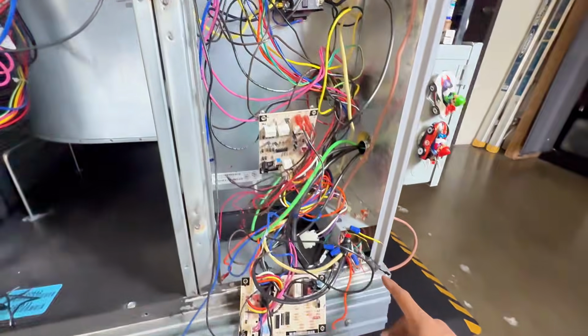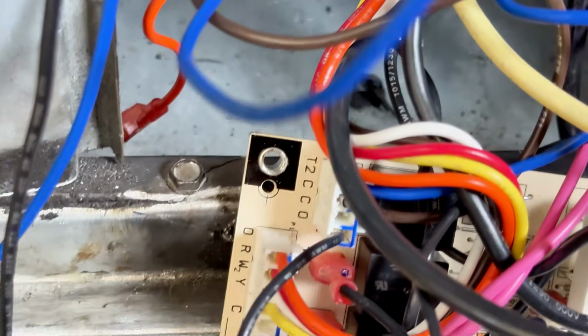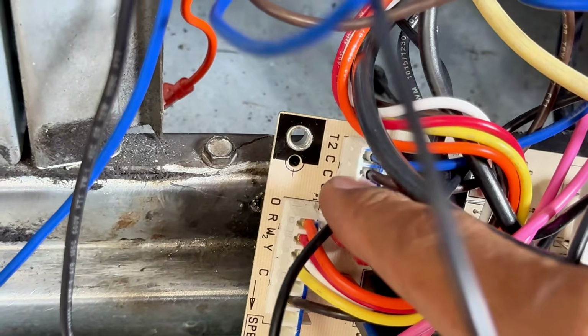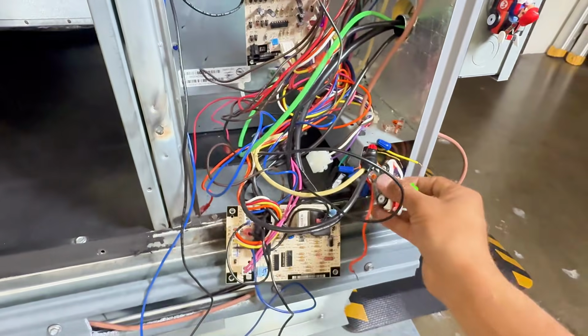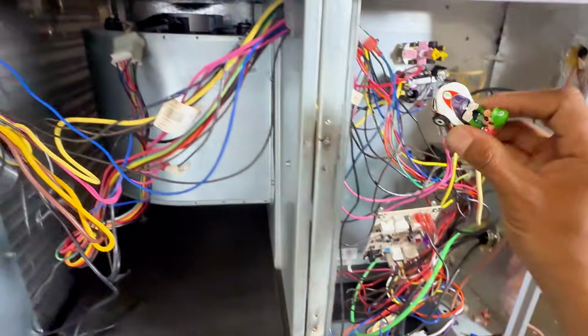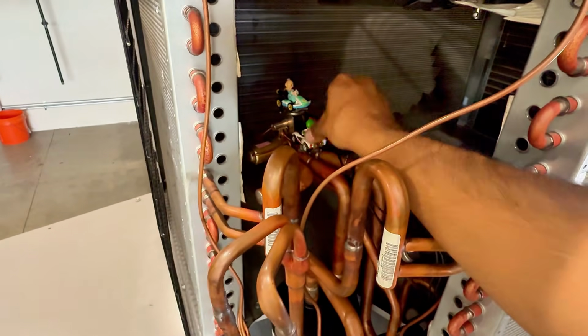So yes, even though it starts off as orange, it goes here to my reversing valve, to the board, the defrost board. It goes in as orange, and it comes out as black. So yes, Luigi takes that route. So Luigi's gonna go like that. He's gonna go like that. Boom, go like that. Go through the black wire all the way, and he's already here with Rosalinda. Boom, 24 volts to the reversing valve.